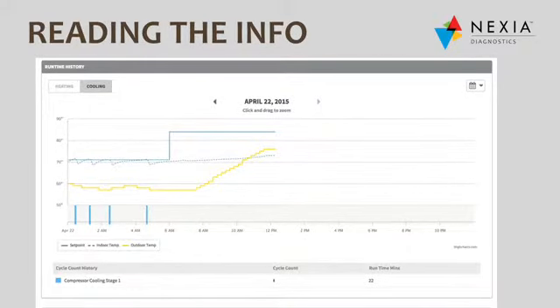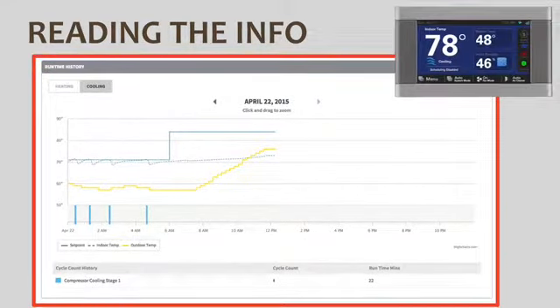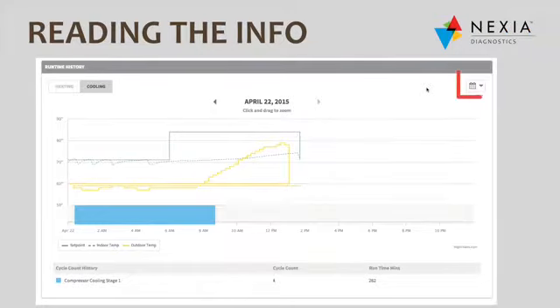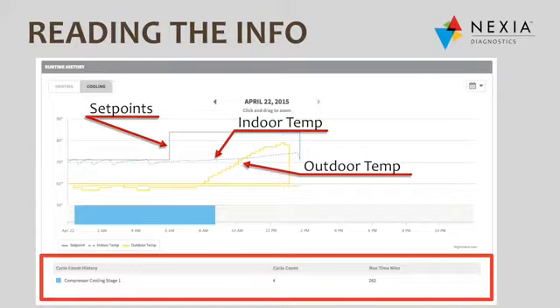A runtime history graph is displayed for 824 and 850 controls and provides up to 30 days of data for the heating mode and the cooling mode. You can scroll from day to day using the right and left arrows, or you can jump to a specific date using the Date Selection tool in the upper right-hand section of the window. The graph includes the indoor temperature, heating and cooling set points, outdoor temperature, heating or cooling operation per stage, and a visual indication of any alert that is present. At the bottom of the graph, a cycle count history is provided for the last 30 days. The number of cycles and sum of the cycle time in minutes is provided.